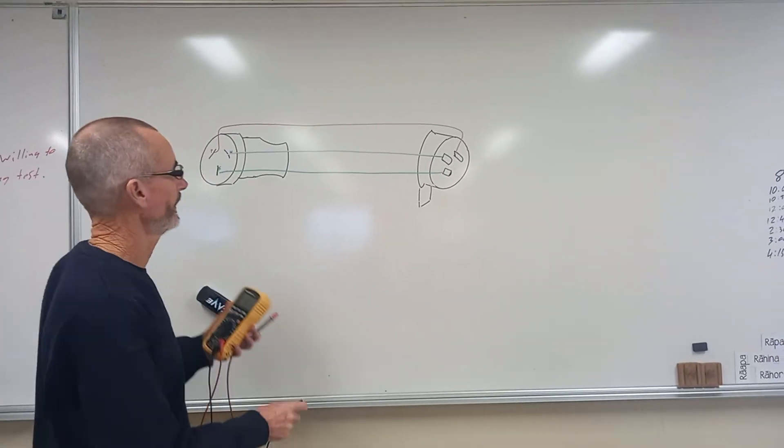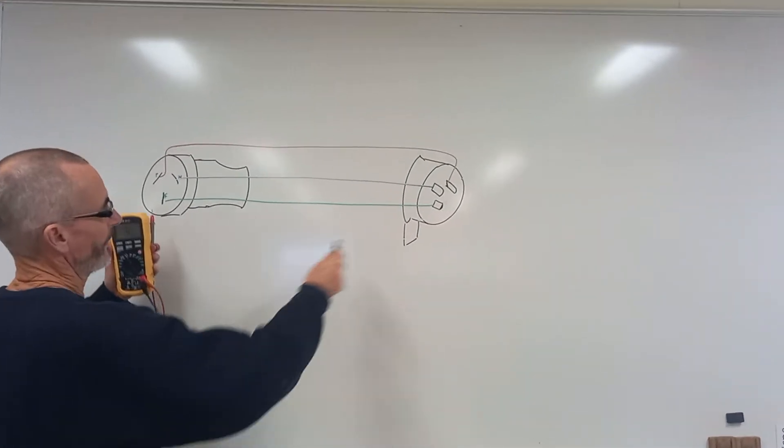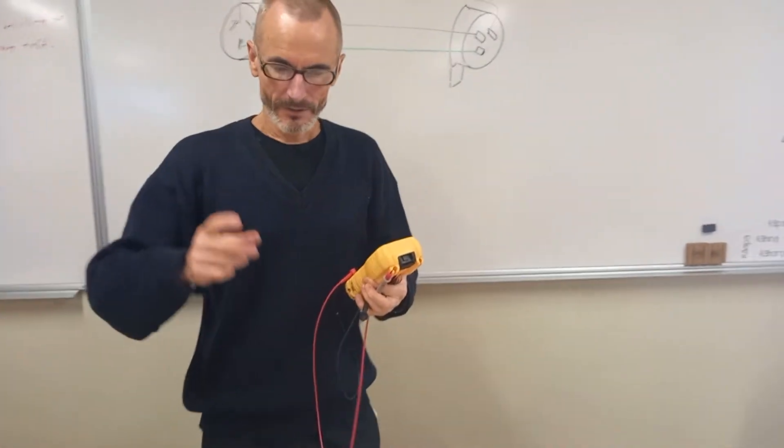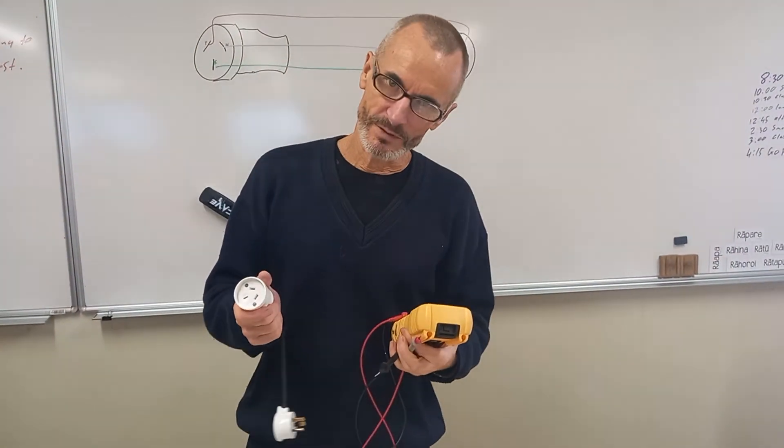There you go, and my first step would be Earth to Earth, neutral to neutral, phase to phase. So there are two tests going on there: there is polarity and continuity.